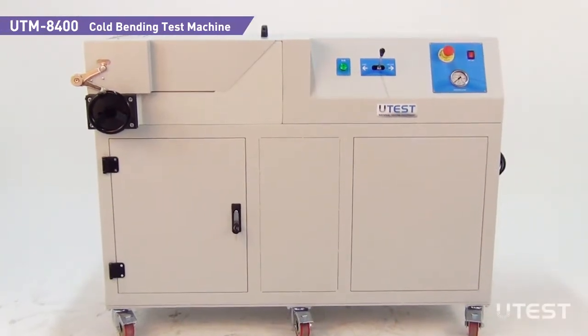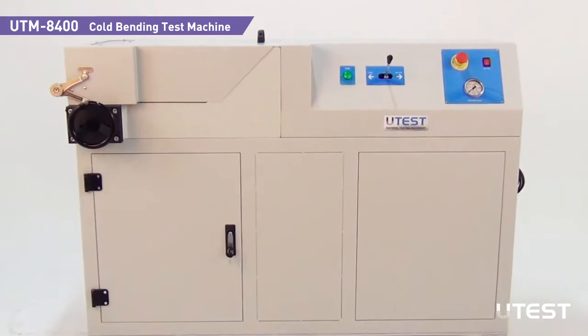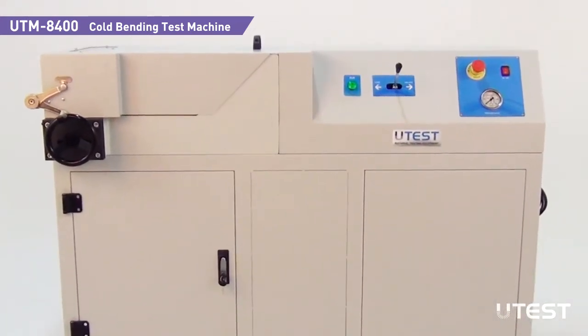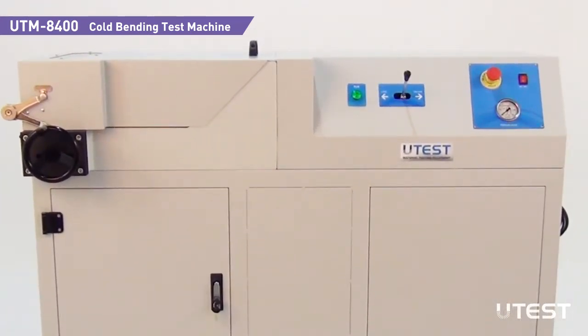UTEST UTM8400 cold bending test machine is used for bending and re-straightening of reinforcing steel bars and it has a loading capacity of 150 kN.